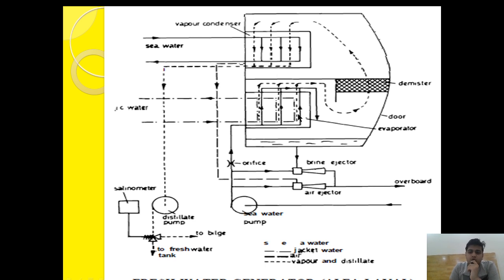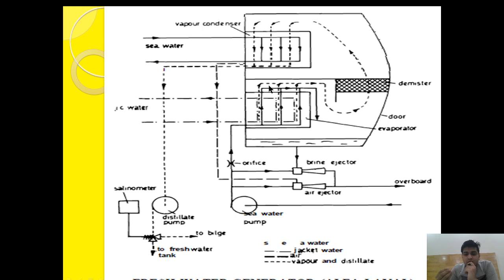This temperature is sufficient for boiling the water, as the condition inside the shell is maintained at vacuum. When the pressure decreases, the boiling point temperature also decreases, so the boiling point of the sea water decreases to 45 to 60 degrees Celsius. Therefore, the jacket water temperature of 75 to 80 degrees is sufficient enough to boil the sea water. During the heat exchange process in the evaporator, the sea water exchanges heat with the jacket water and converts into vapor form — distillate water vapor.